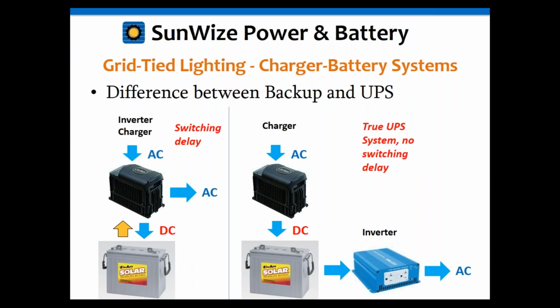This can be a problem with any UPS system, not just lighting in particular. And I know that's a problem for some loads, that they see that blip for that transfer. It causes their stuff to reboot, which was kind of the whole point to have the UPS. So just something to keep in mind. Some inverter chargers can have a very high switch rate, which means that they can be like a half a cycle or so, and some of the loads can handle that. Some may be longer than that. There may be 2 or 3 cycles for the switch delay, and that may be enough to cause the loads to reset. So again, you just need to know your loads and whether it's critical or not, and whether that delay is going to be an issue or not.